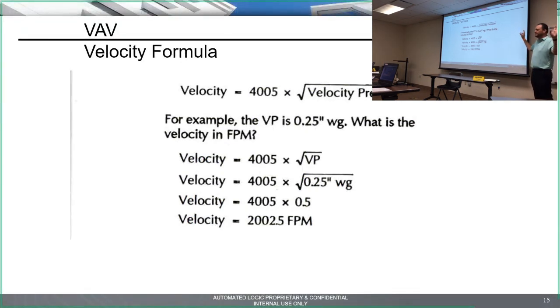So, math class, no, I'm just kidding. In order to figure out what the velocity of the air is, it's a simple formula. The VAV box measures the total pressure, subtracts the static pressure, and gets the velocity pressure. Using this formula, 4,005 times the square root of the velocity pressure, this is a constant, and it's derived from a formula this long, but you don't have to know that. 4,005 times the square root of the velocity pressure gives you feet per minute. So if I measure 0.25 inches, because we measure static and total pressure in inches, take the square root of that, you end up with 0.5 times 4,005, which is 2,002 feet per minute. All right? It's just a math equation. Going to the next one.